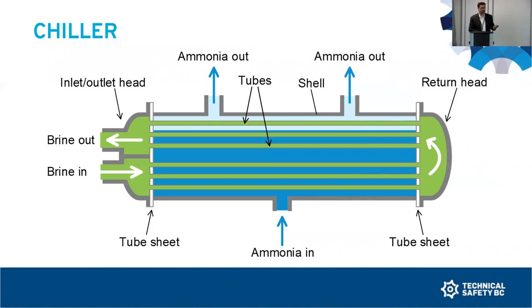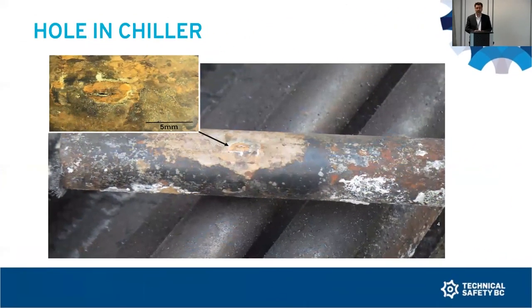We found a very small hole in the vapor section, located right about there near the return head of the chiller, up high in one of the elevated tubes. It's a very important thing to understand, because small holes in those types of locations are a lot more common than any sort of major failure. So it's an important learning for our industry, and it changes the way we have to understand those types of failures or leaks that might be occurring.